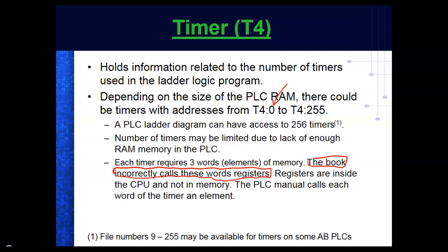Do y'all understand that? So the big difference between this guy and newer PLCs, and the newer programming applications like 5000 and TIA Portal, is that the memory is how you set it up. So if you want a timer, you put a timer in there and it eats up the memory for a timer. But on the 500, since they wanted to make this easier for people that did not understand computers, the PLC manages the memory, or the application manages the memory. So if I set up another timer file, then basically I'm dedicating another 256 times 3 for counters and timers. But it makes it easier for us to explain and understand the memory.